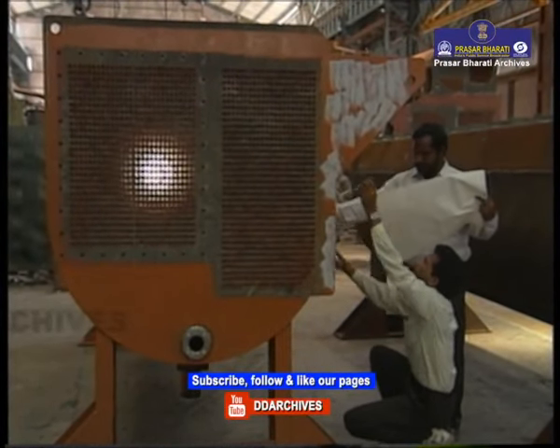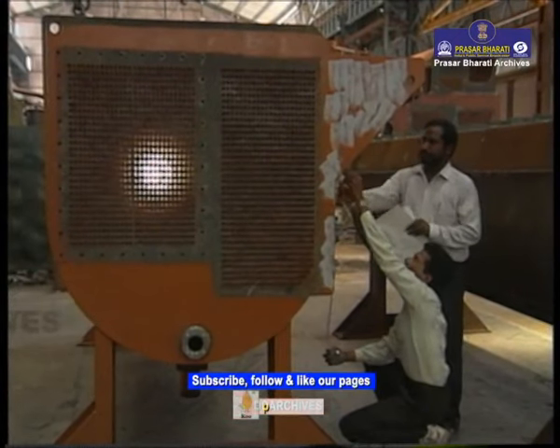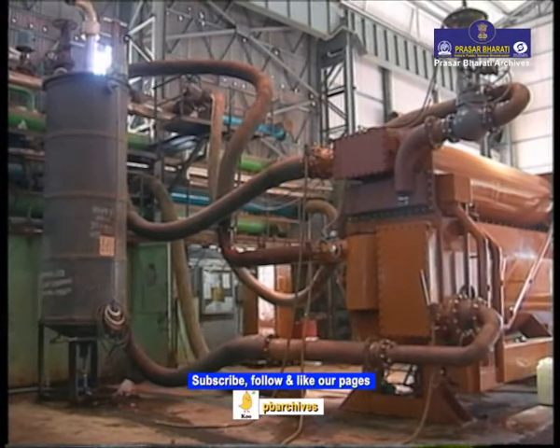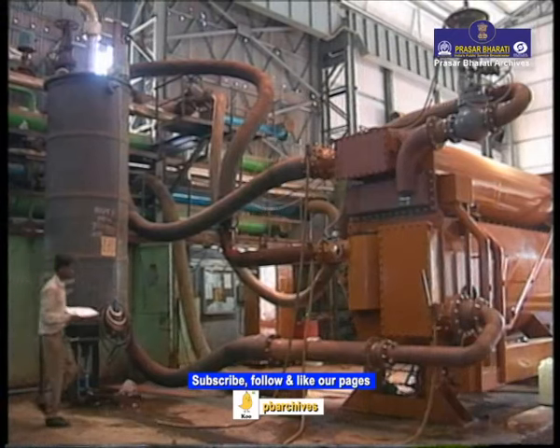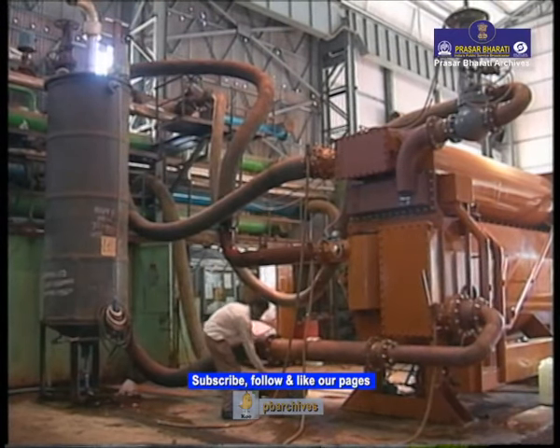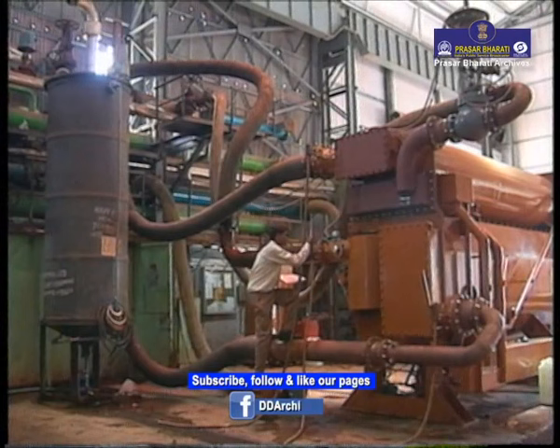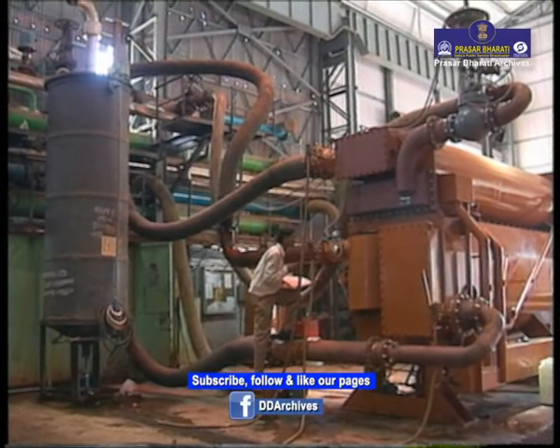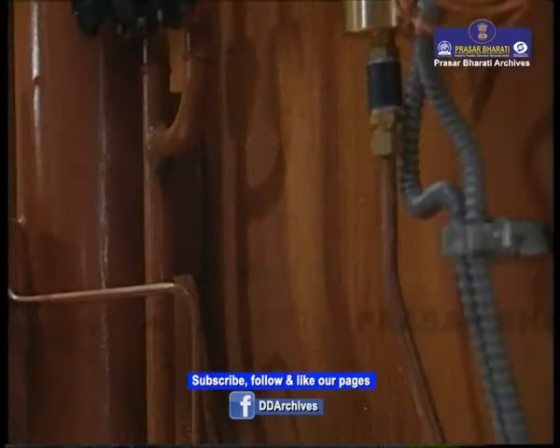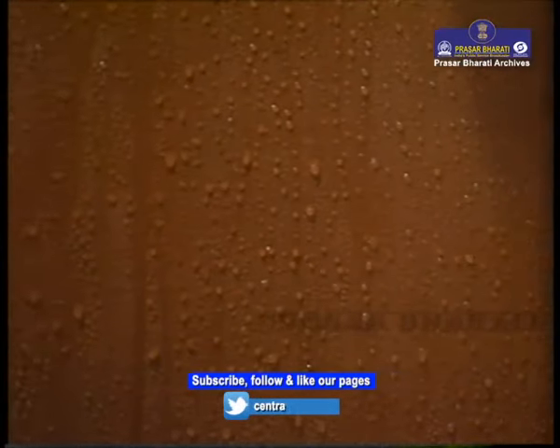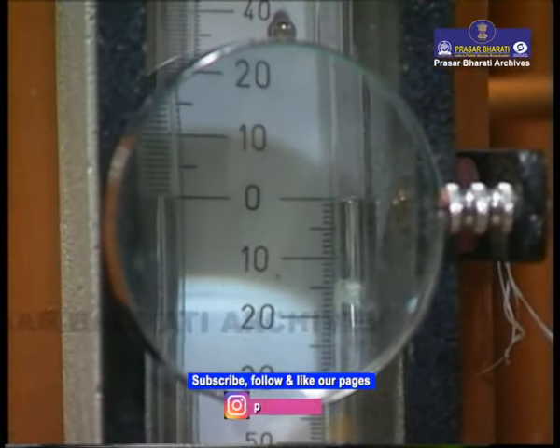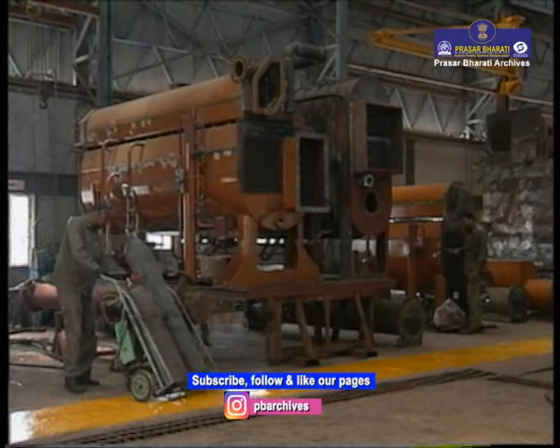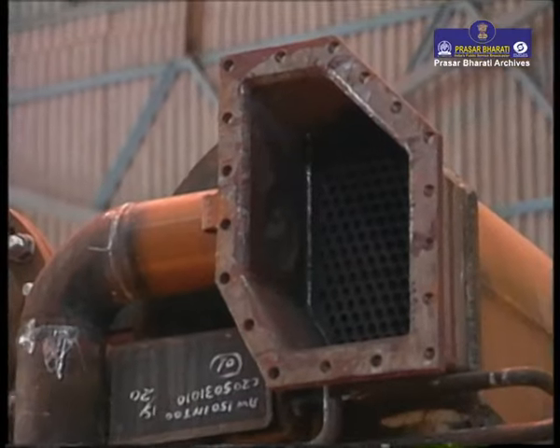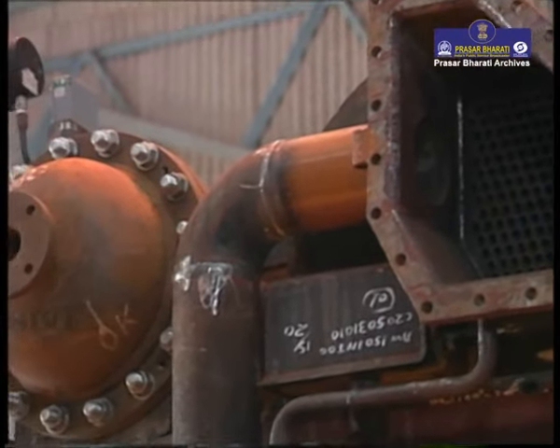Any refrigeration system is based on the fact that an evaporating liquid absorbs latent heat from its vicinity. A closed loop of continuous evaporation and compression makes up a refrigeration system. In a vapor absorption chiller, water, which is the refrigerant, is sprayed in a vacuumized chamber. In partial vacuum, water boils at 3 to 4 degrees centigrade and thus absorbs heat from the water flowing through the chamber in copper tubes, in the process chilling it.